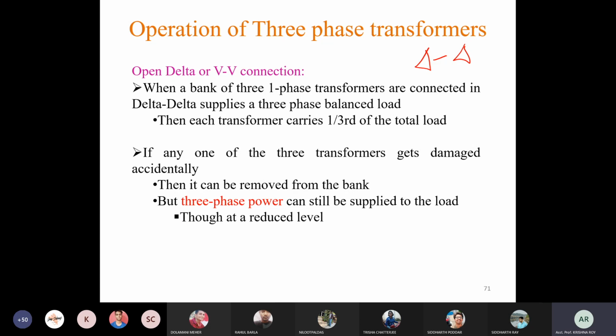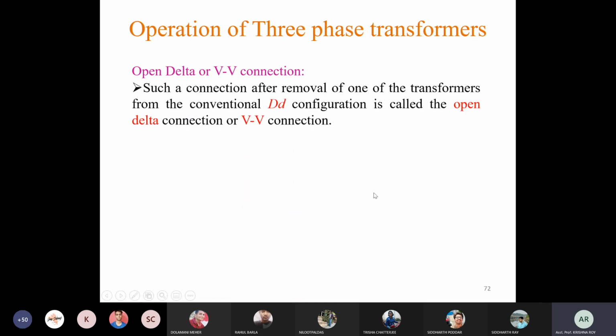Reduced level means the capacity of the remaining two transformers, we cannot use their full capacity. We will be able to supply at a reduced level, meaning we will not be able to use the full capacity of the two remaining transformers. That we will see later on. Okay, so after the removal of this faulty transformer, this new formation is called the open delta or VV connection. Such a connection, after removal of one of the transformers from the conventional delta delta configuration, is called the open delta connection or VV connection.